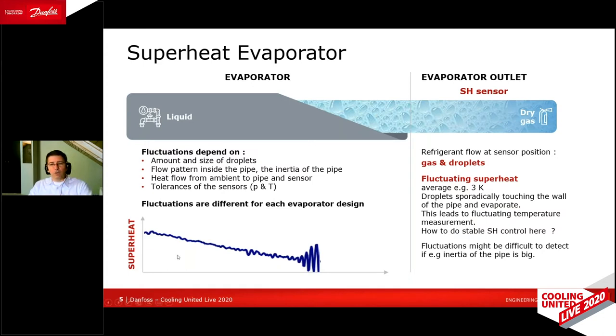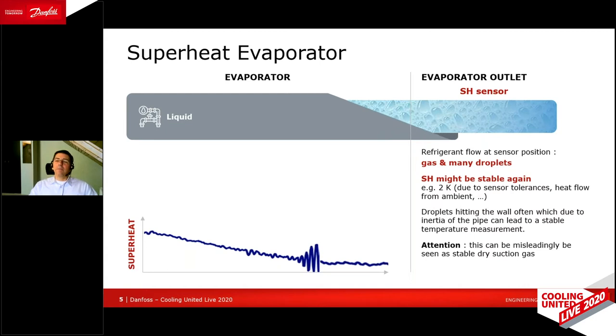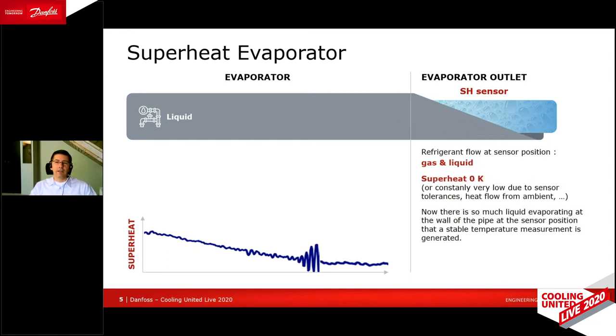But just to show what can happen, let's reduce even further. Many more droplets come out of the evaporator, and all of a sudden the superheat measurement can look like it is stable again. But now it is stable wet gas leaving the evaporator, which is not good — it is misleading. Many droplets are coming out, and this stable measurement can come from sensor tolerances because we actually have zero superheat. If we reduce even further, thinking we are on a stable dry superheat, we get a really large amount of liquid out of the evaporator, and that needs to be avoided.